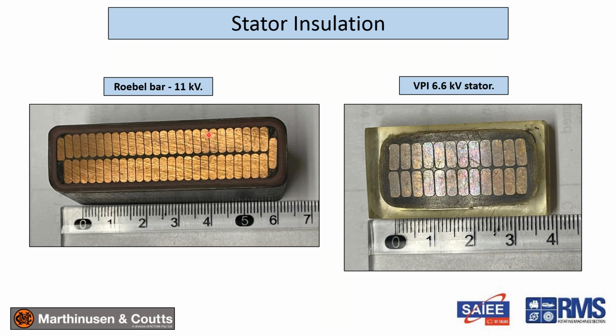So now we look at a typical stator. Two typical stator coils, samples from coils. This is actually a resin rich bar, it's not a VPI bar. You can see here it's 11 kV. I've put a ruler there to show you the clearances, and you'll see the relevance of this later. So that's probably about 3 millimeters. It's a Roebel bar, so this is a single turn.